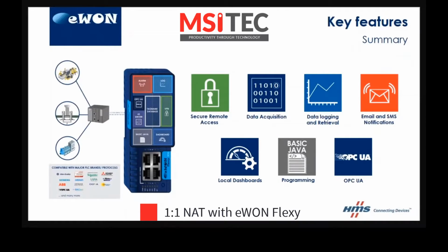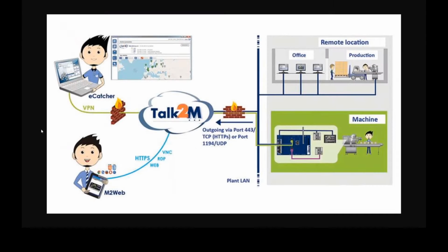Today we're going to be discussing a pretty commonly requested setting on the Ewon Flexy. Typically, Flexys are added to an existing industrial network for remote access and/or used as a cellular gateway for some edge devices. In the setting on screen, they've added the Ewon to an existing industrial network. By default, it will only allow non-VPN traffic in one direction, from the Flexy's LAN, the green section on the picture, to the Flexy's WAN, the blue lines on the picture. Usually this would be the industrial network.